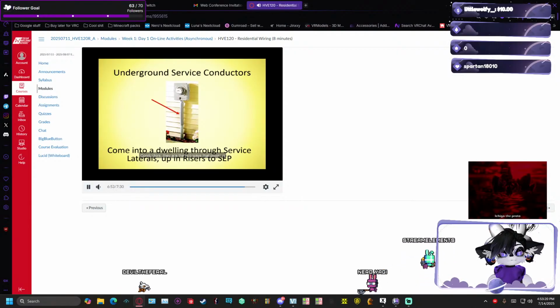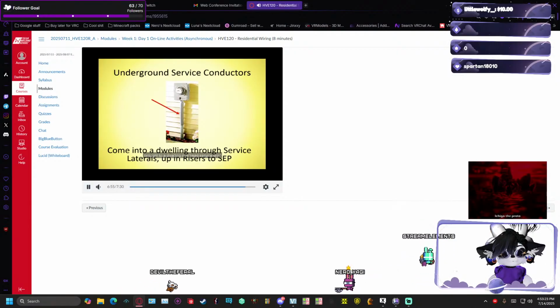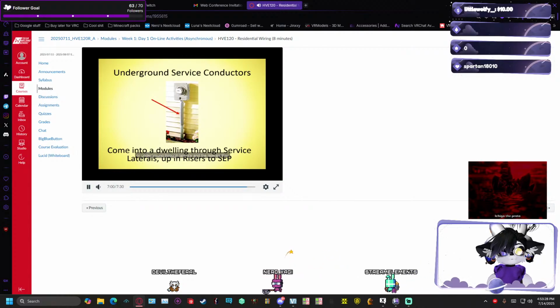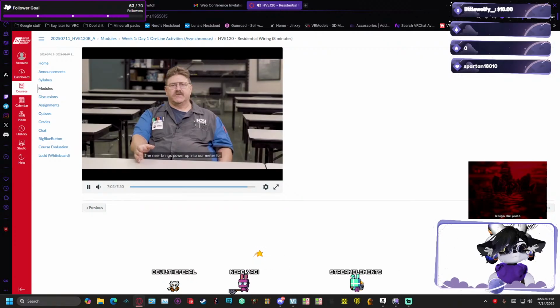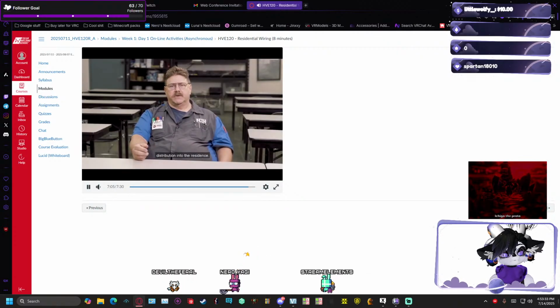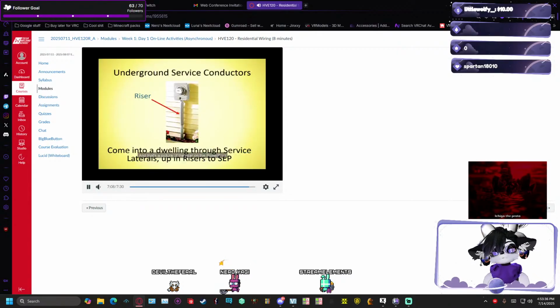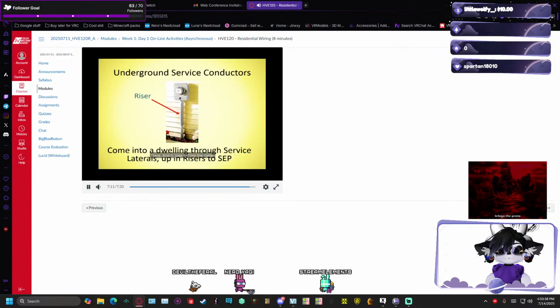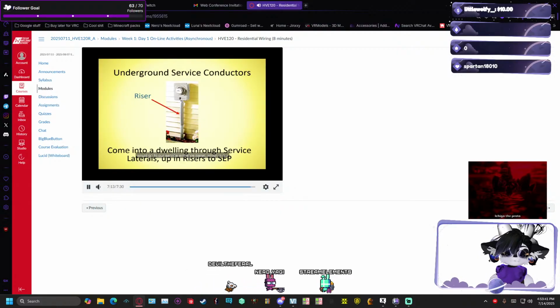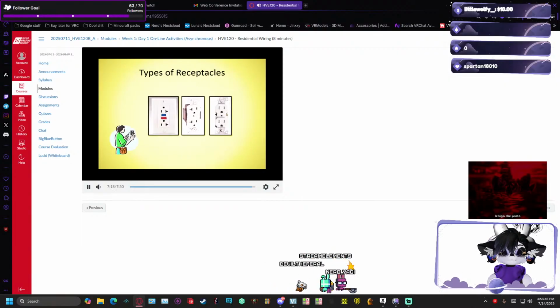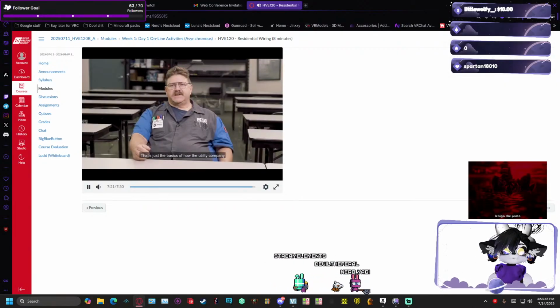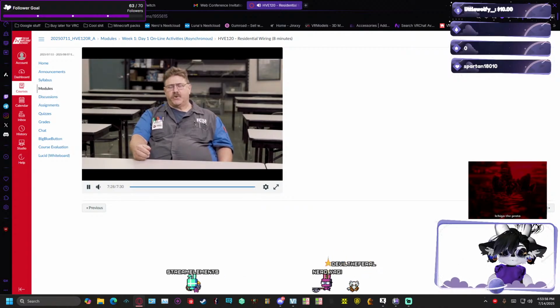This is an underground service conductors. They are the two ways that power is brought to a dwelling: overhead service drop or underground through laterals. And the laterals then come to a riser. The riser brings the power up into our meter for distribution into the residence. And that's a picture of the riser on the PowerPoint there. And from the meter, we go to our service entrance panel, which is our breakers and our overcurrent protection. That's just the basics of how the utility company brings the power and what we use and how it gets from their generating stations to our residents.